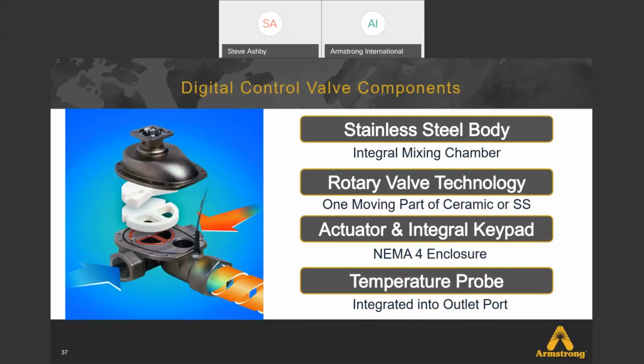So this is a very simple valve. There's not a lot going on as far as parts and pieces all working in conjunction. Again, we talked about the stainless steel body, and then you can see the bonnet is a kind of concave design. That is what we call an integral mixing chamber. As the water comes in on your hot and cold side, it makes a 90-degree move into the valve body, and it creates a swirling motion in the bonnet area itself. So mixing takes place in the valve itself, continues to mix as it leaves, and we're able to put the temperature probe right in the valve outlet itself.